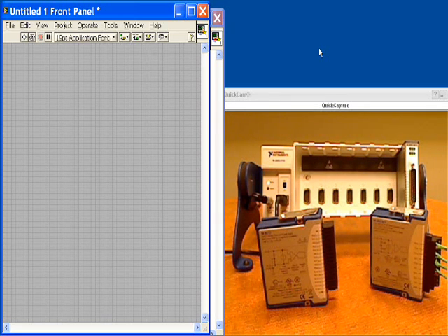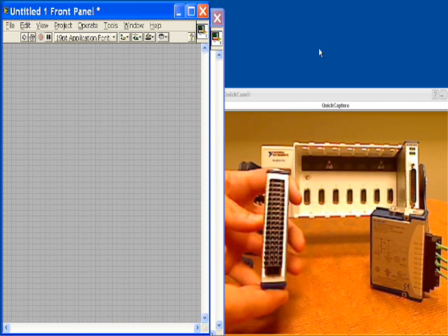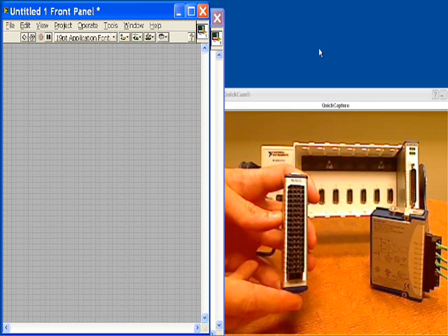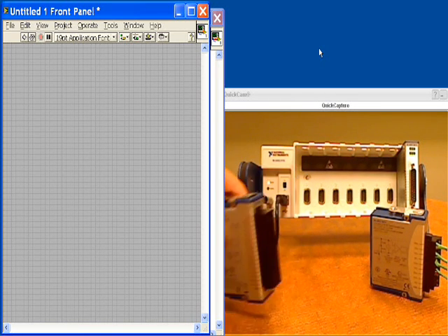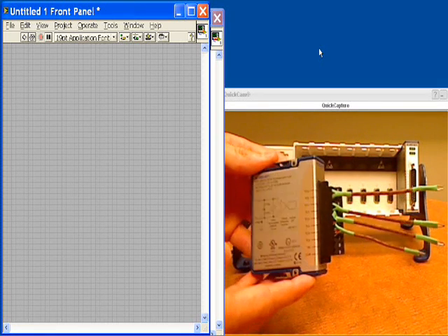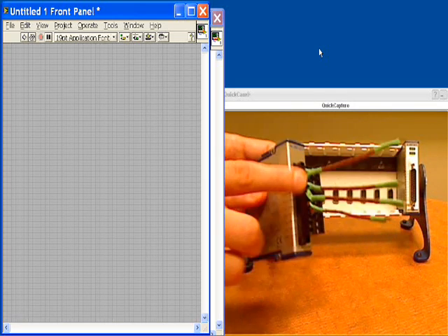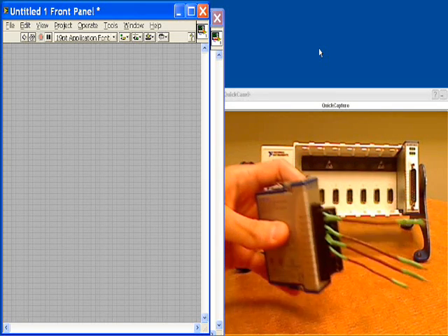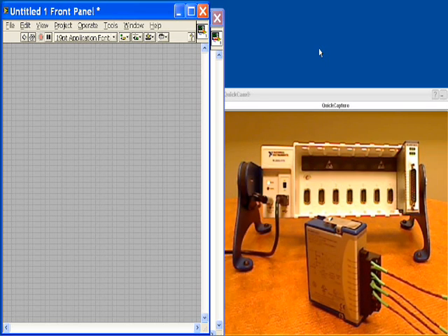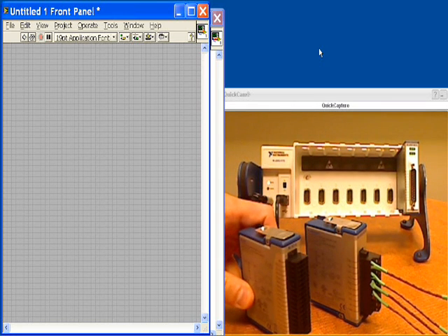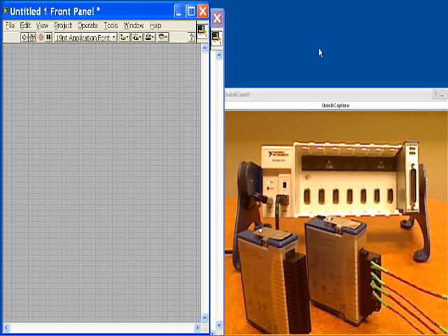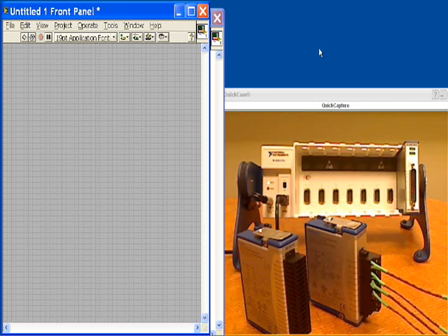For thermocouple measurements in the C-Series modules, we have a few different options. One is the 9213 16-channel module for high-density thermocouple solutions, and the other is a 4-channel version, the NI 9211. You can see we've already got four thermocouples connected to it. Both of these modules are 24-bit resolution, have built-in cold junction compensation for more accuracy, and can connect to a variety of thermocouple types such as K, J, T, etc.